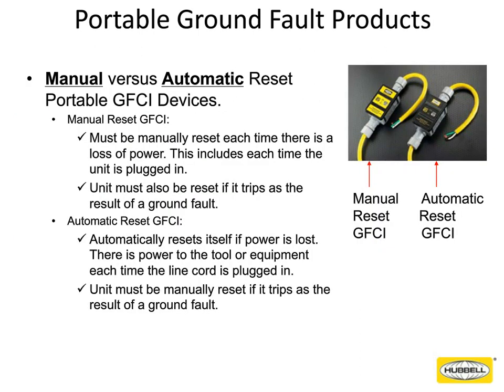Within portables, there's also two varieties of portables, and it's important to understand the difference. Every manufacturer, not just Hubbell, makes both manual and automatic reset portables. So I want to spend a minute making sure you understand the difference and where you should use each. A manual reset unit requires you to reset the ground fault every time you plug it in. So every time you unplug it, put it back in the storeroom, and go to use it again, you must reset the ground fault the minute you provide power to it.